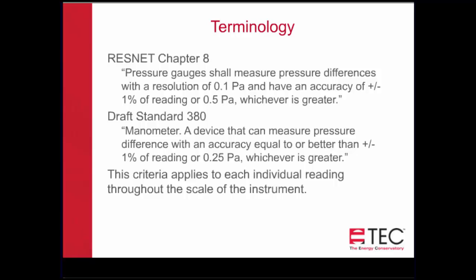Now, ResNet also talks about what the instrument should be capable of. So pressure gauges shall measure pressure differences with a resolution of 0.1 Pascal and have an accuracy of plus or minus 1% or half a Pascal, whichever is greater. The new standard says that the device can measure pressure difference with an accuracy equal to plus or minus 1% or 0.25 pascals, whichever is greater. So in the new standard, it's actually a little bit tighter than the previous standard. So any instrument that's used for measuring pressure has to meet this new standard 380 criteria.